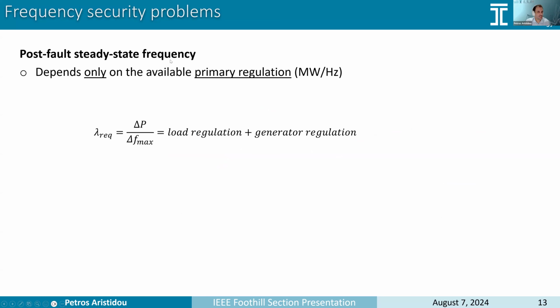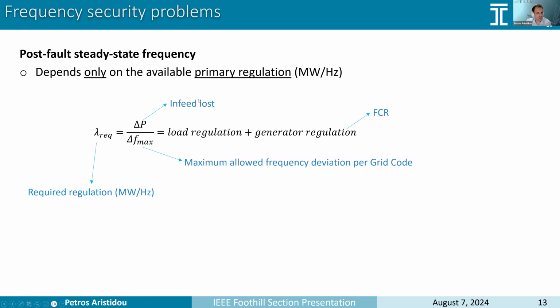If we go to the post-fault steady state frequency, again we can use the equations that we showed before. And we see that it depends only on the available primary regulation. Again, we have here the in-feed loss, so this is the lost power that we consider. And here is the maximum allowed frequency deviation per the grid code. In Cyprus, that's 0.5 hertz. And this depends on the load regulation, so the normal regulation, the sensitivity of the load towards frequency deviation, and the generator regulation, which is the frequency containment reserves. Again, using these, we can compute the amount of frequency containment reserves that we need in the system in order to comply with the requirements on the post-fault steady state frequency.